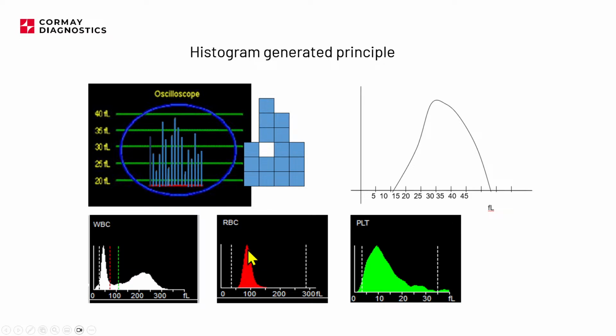The device can also measure the MCV value, which is mean corpuscular volume of the red blood cells. So this is basically, usually, the mean size of the red blood cells. The device can also calculate parameters like RDW-SD and RDW-CV, and those are basically the width of this distribution curve in two positions, like here and here. And according to this information and according to the hemoglobin concentration, other parameters can be reported by the analyzer.